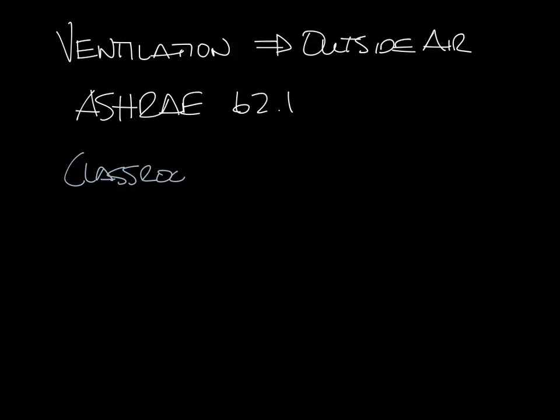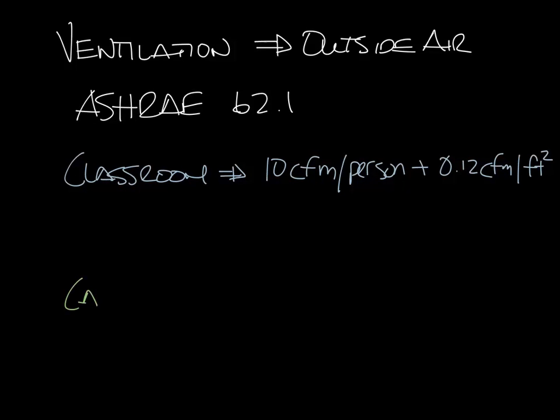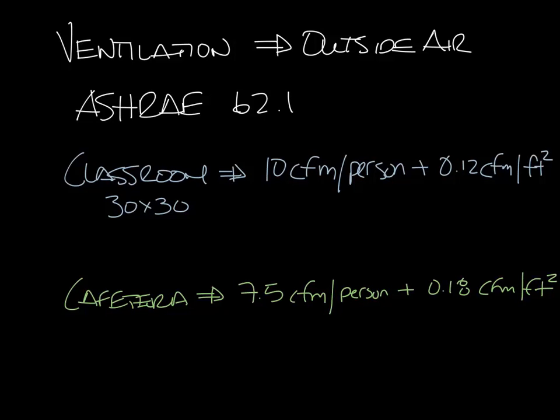For instance, ASHRAE 62.1 says that a classroom needs 10 CFM per person plus 0.12 CFM per square foot, and a cafeteria would need 7.5 CFM per person plus 0.18 CFM per square foot. So if we have a classroom that's 30 by 30 with 30 kids in it, that would be 30 times 30 equals 900 square feet times 0.12 plus 30 kids times 10 CFM is 300, and that gives you 408 CFM of fresh air.